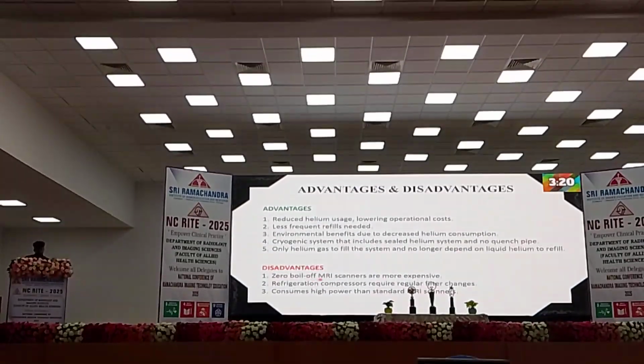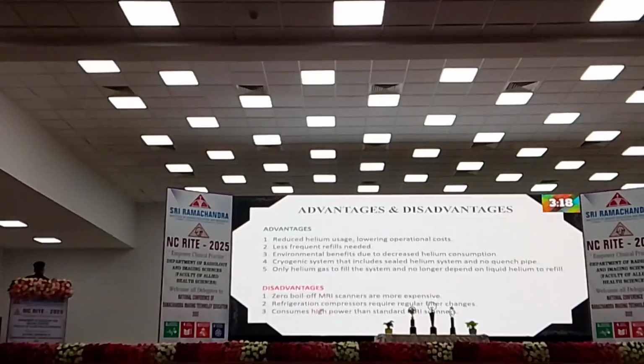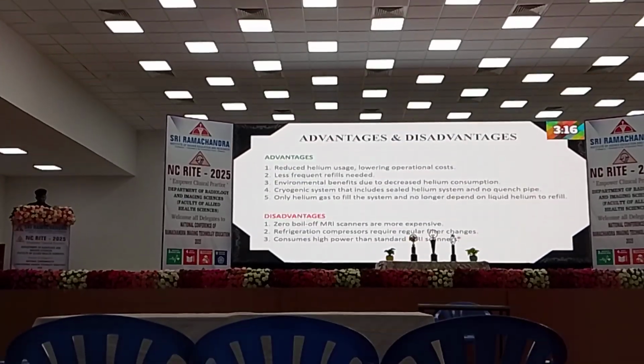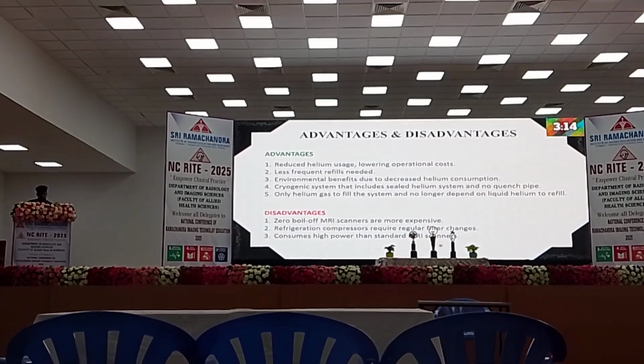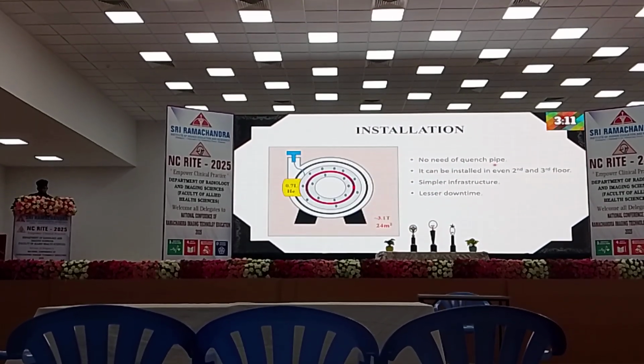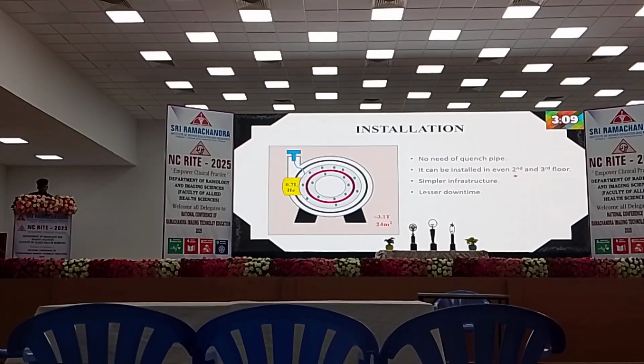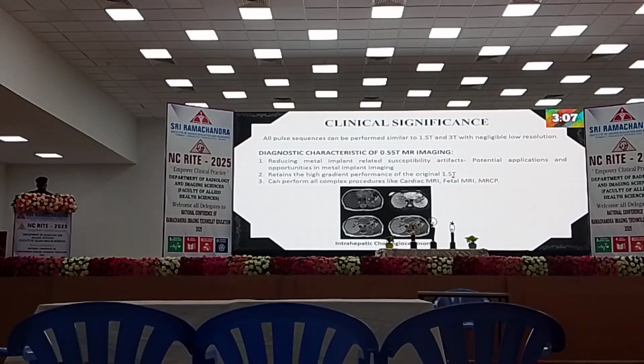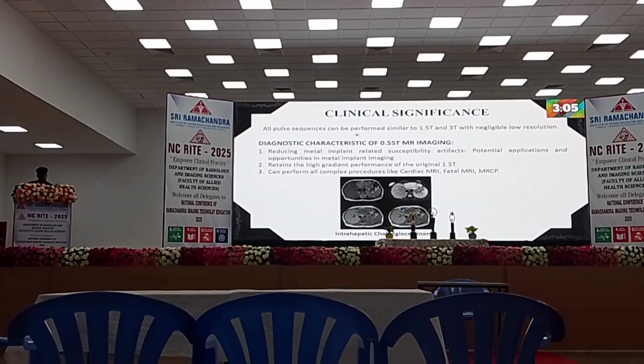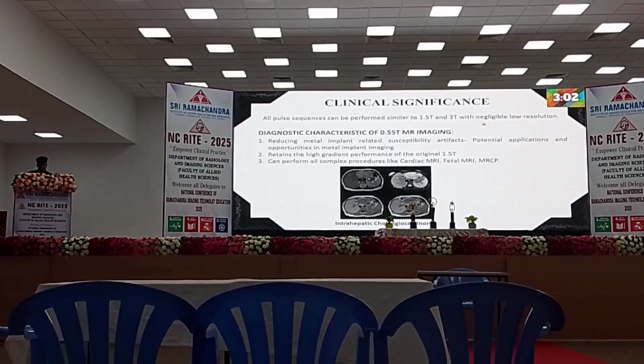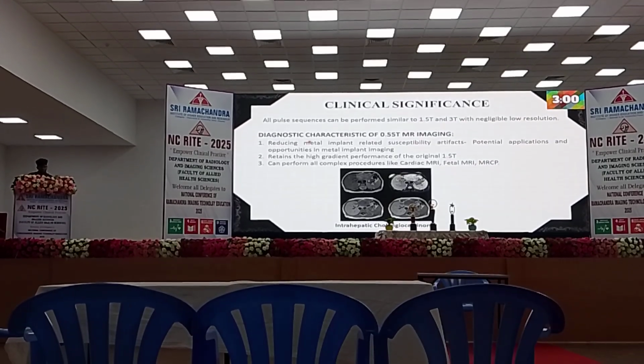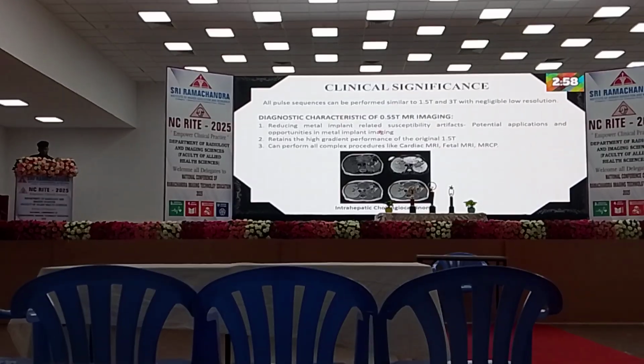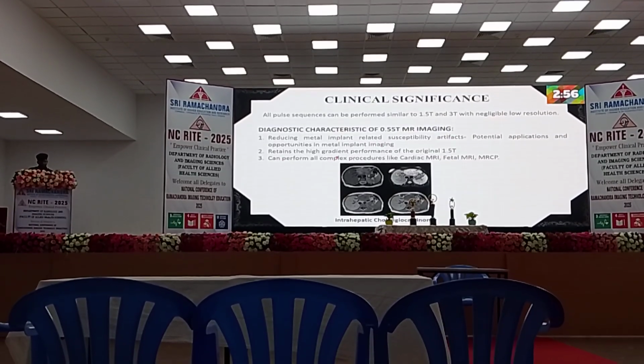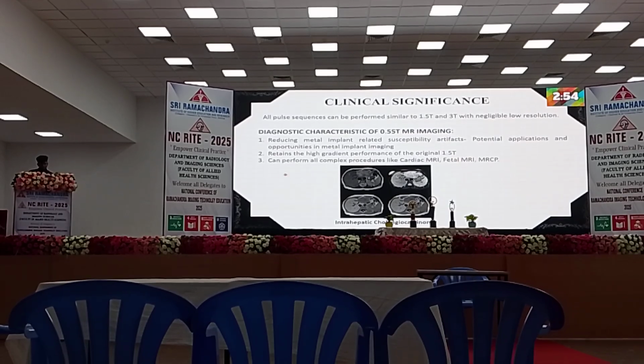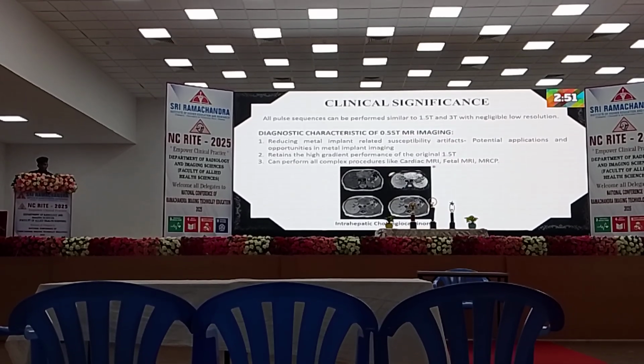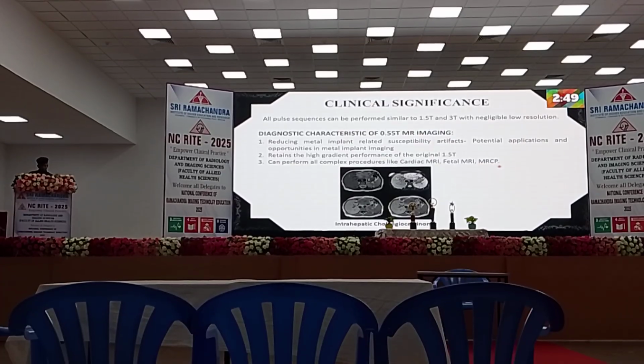Disadvantages are that zero boil-off MRI scanners are more expensive, the refrigeration compressor requires regular filter changes, and it consumes higher power than a standard MRI. Installation. No need for a quench pipe. It can even be installed on the second or third floor, with simple infrastructure. All pulse sequences can be performed similar to 1.5 and 3 Tesla with negligible loss of resolution. Diagnostic characteristics are reduced metal implant related susceptibility artifact, retaining the high gradient performance of the original 1.5 Tesla, and it can perform all procedures like cardiac MRI, fetal MRI, MRCP, etc.